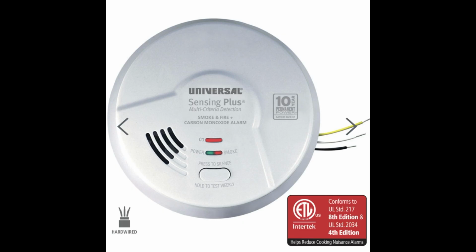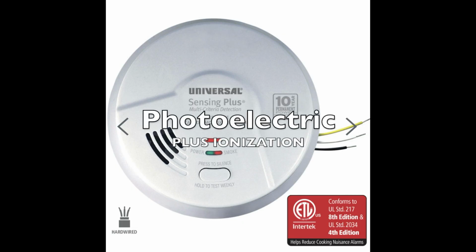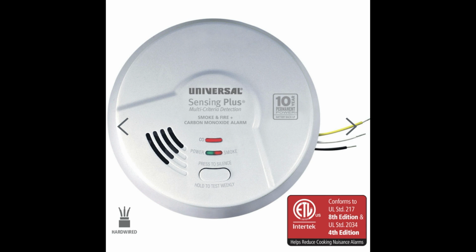That's why a recommended approach is to use combination smoke detectors that include both photoelectric and ionization sensors. This provides comprehensive protection, as the combination can detect both slow smoldering and fast flaming fires effectively. However, given their higher propensity for false alarms and less effectiveness with smoldering fires, ionization-only detectors may not be the best choice for certain residential uses.